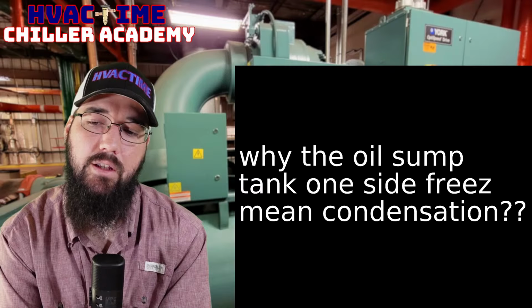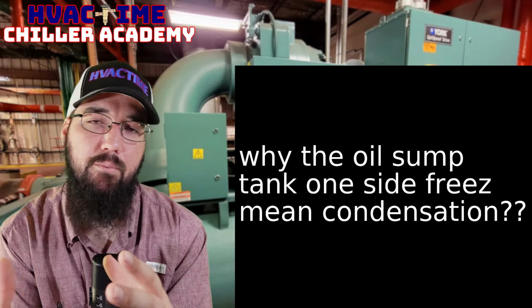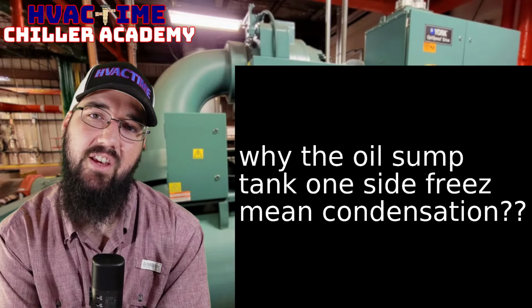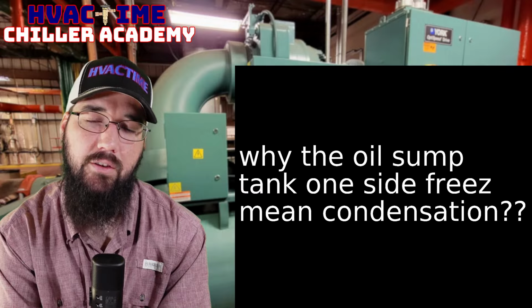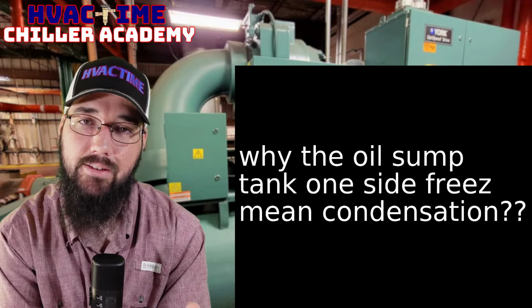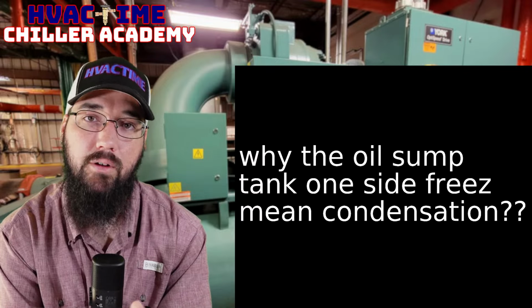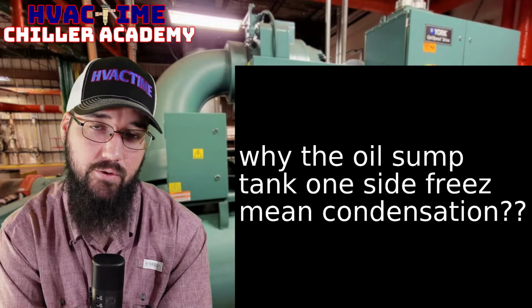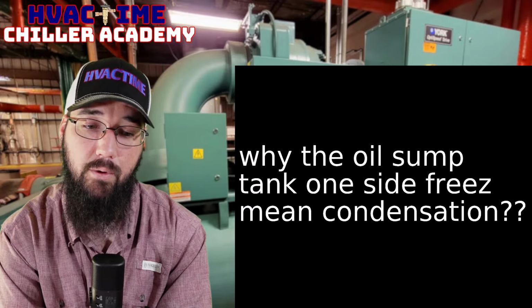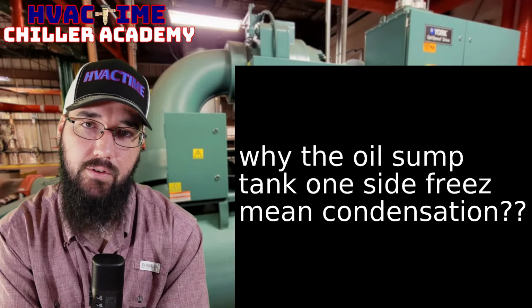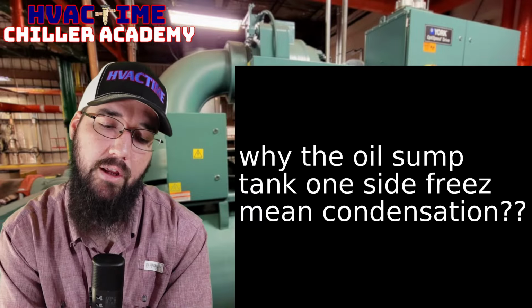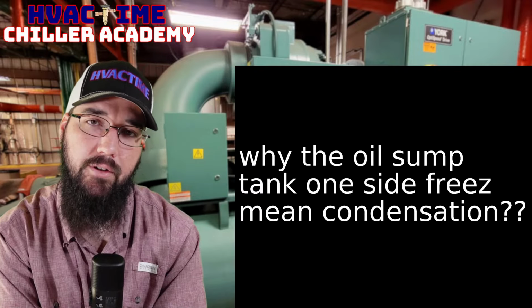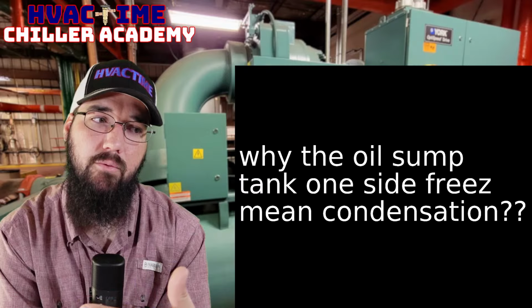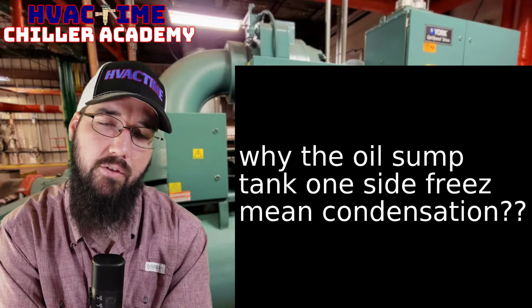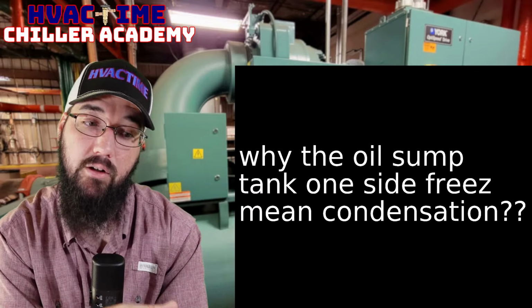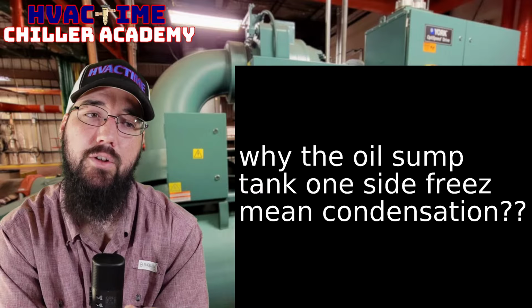So that's just between those two models alone, two examples of what you'll see when you start seeing the eductor or the sump, the tank itself, begin to condensate or actually ice over and sweat, anything of that nature. In my experience, it has always been because of the eductor system or the oil return system, and we're bringing too much liquid refrigerant back, and it's overloading the circuit.